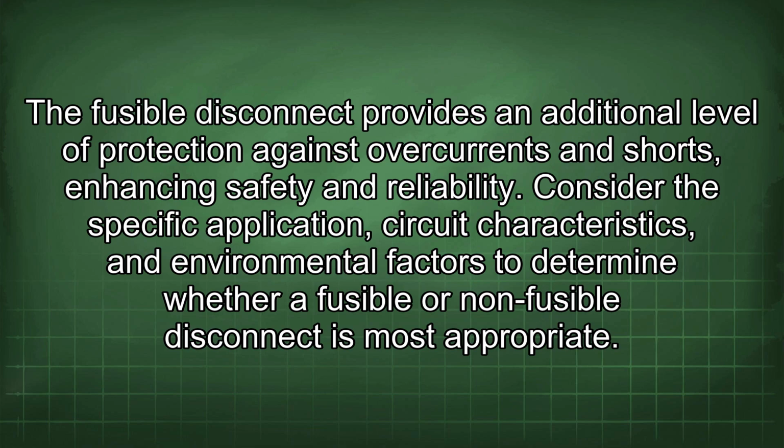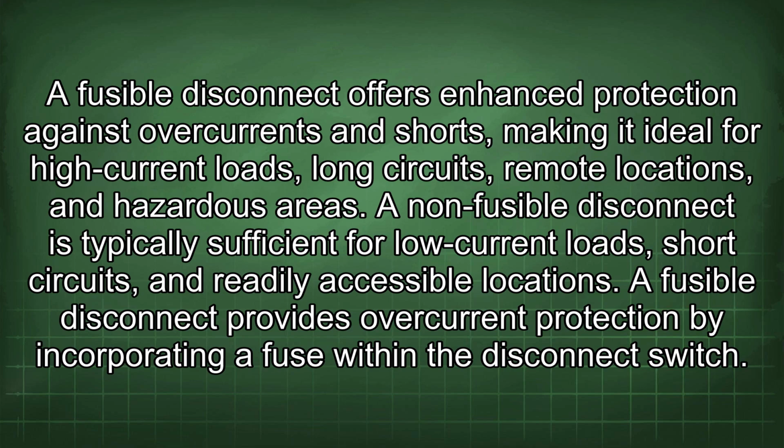Consider the specific application, circuit characteristics, and environmental factors to determine whether a fusible or non-fusible disconnect is most appropriate. A fusible disconnect offers enhanced protection against overcurrents and shorts, making it ideal for high current loads, long circuits, remote locations, and hazardous areas. A non-fusible disconnect is typically sufficient for low current loads, short circuits, and readily accessible locations.